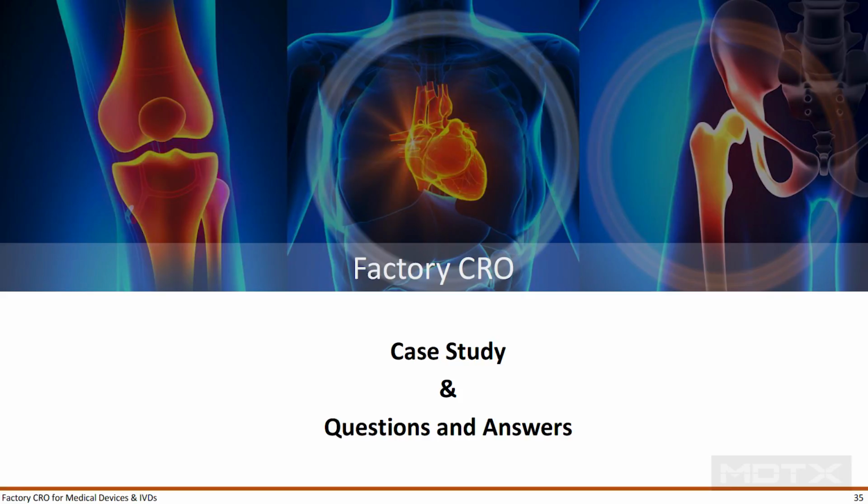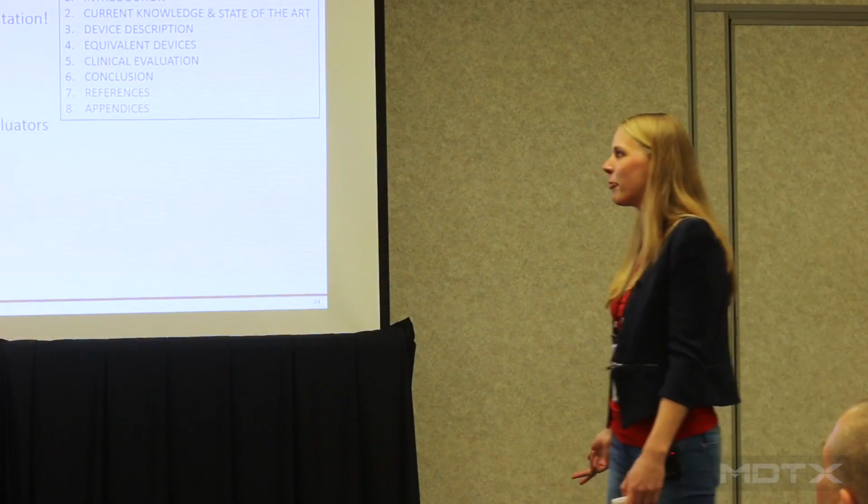Well, then the references and the appendices. Make sure that you have all your literature referenced in your reference list or your bibliography. That's a difficult word for me. And then your appendices: your clinical evaluation plan, your literature review protocol, your literature review report.